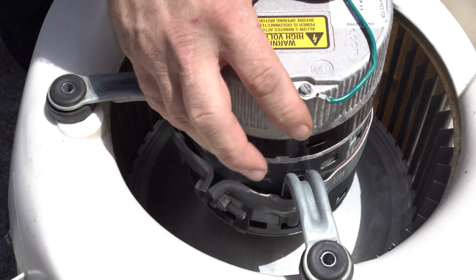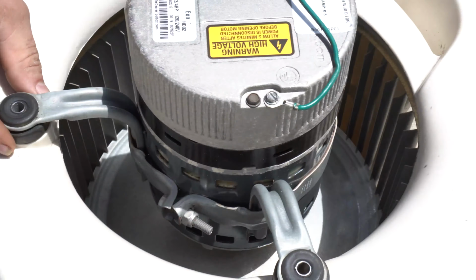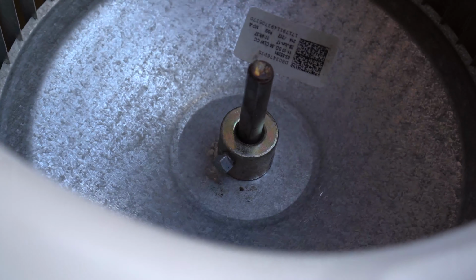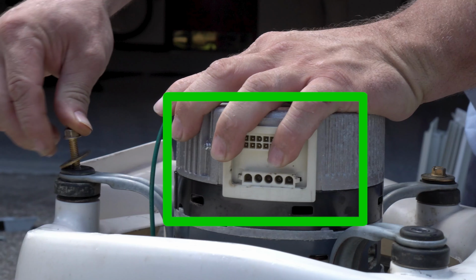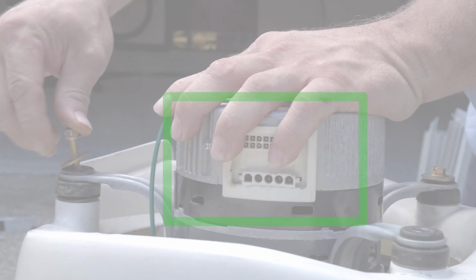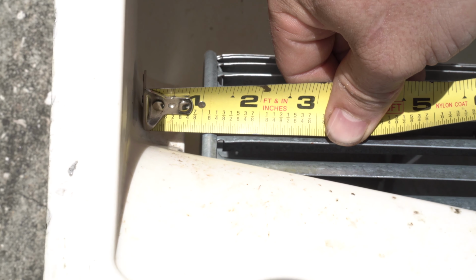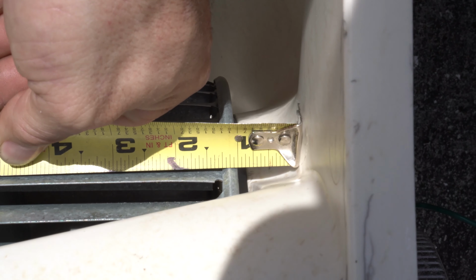When reinstalling the blower assembly, the blower wheel hub with the locking nut should be on the opposite side of the motor. This will assure that you have the rotation of the wheel correct. Do not forget to align the electrical with the mark you added to the blower cabinet. Align the blower wheel on the motor shaft so there is equal distance on each side of the blower wheel.